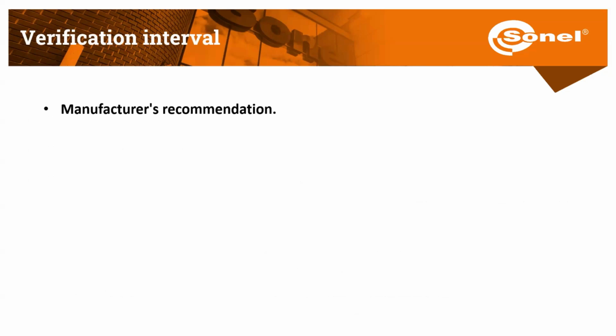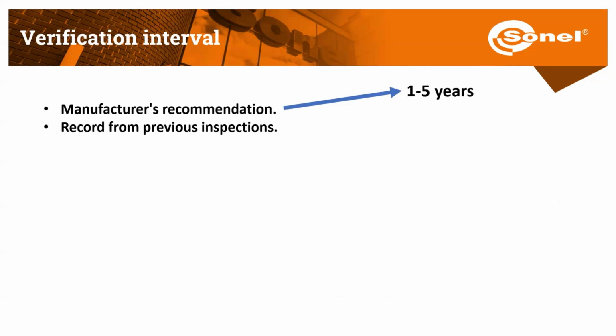We should set the inspection intervals for photovoltaic installation based on several factors, including the recommendations of the manufacturers of the equipment used in the installation, such as inverters or panels. Previous inspection records should also be considered. If we are performing a periodic inspection, such documents will certainly be available. However, for an initial inspection before the installation starts up, this information won't be present.